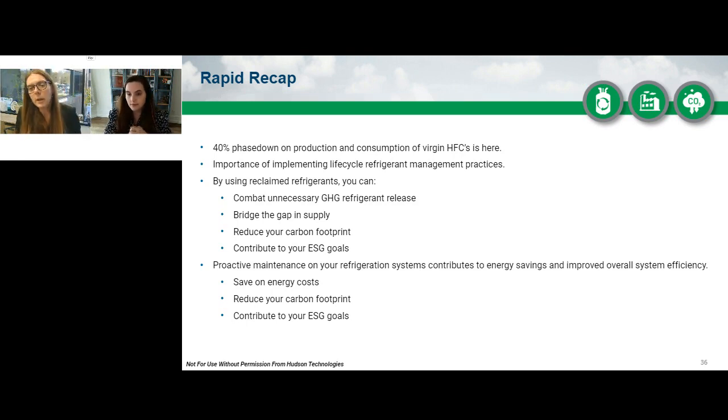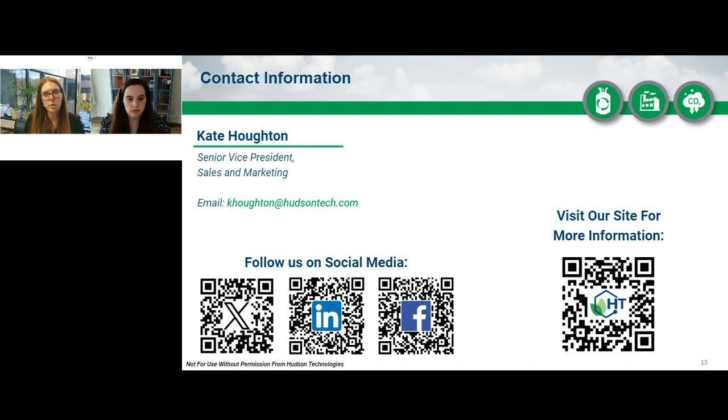Yeah, so the EPA here is looking at F-gas slightly different than the regulations in Europe, so the timeline is slightly different. The industry here is moving towards HFOs. Again, the transition will take some time because of the installed base. Over the next few years, you'll start to see an increase in the use of HFOs here in equipment. Again, a number of those HFOs require new equipment versus being able to retrofit.